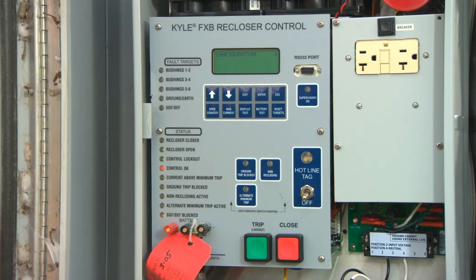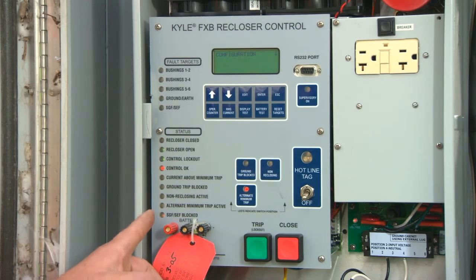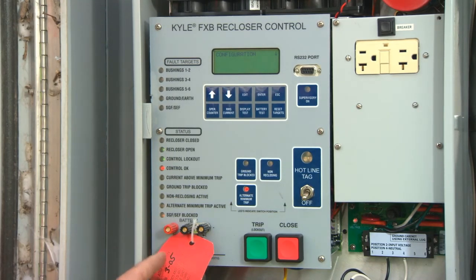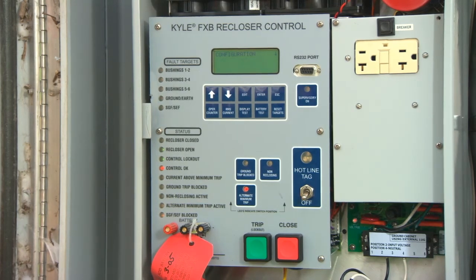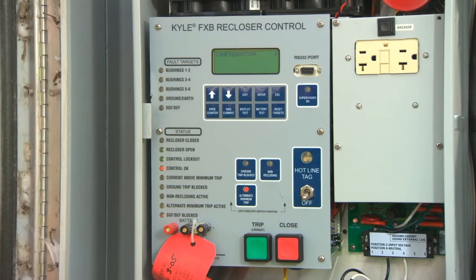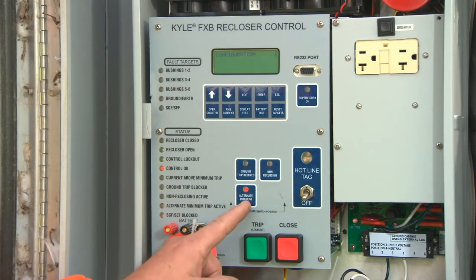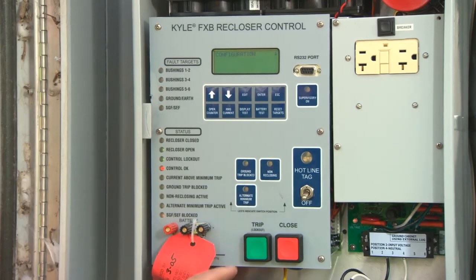If there were a second set of group settings programmed, you would push the alternate minimum trip button. The LED would turn red. You will also see an amber light here on the side, indicating that the second or alternate trip setting is active. These are always programmed at present state with the same settings. To turn it back off, simply press the button.